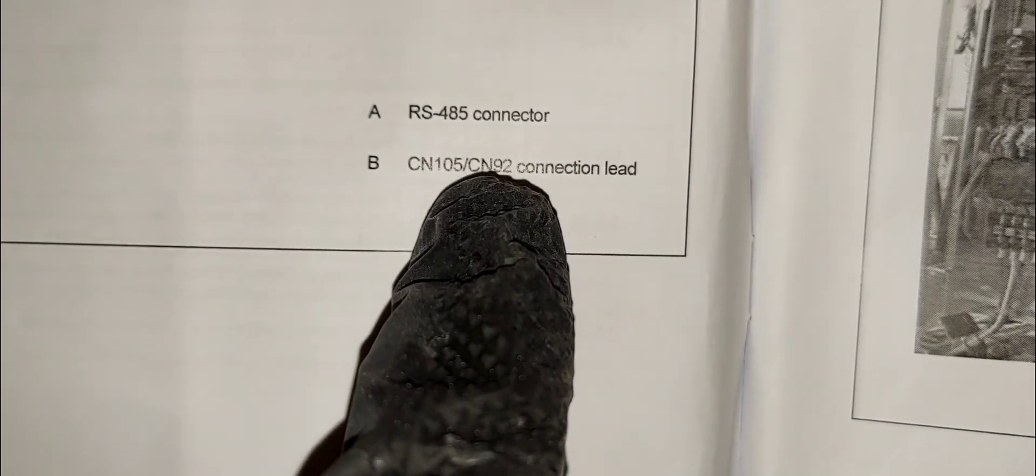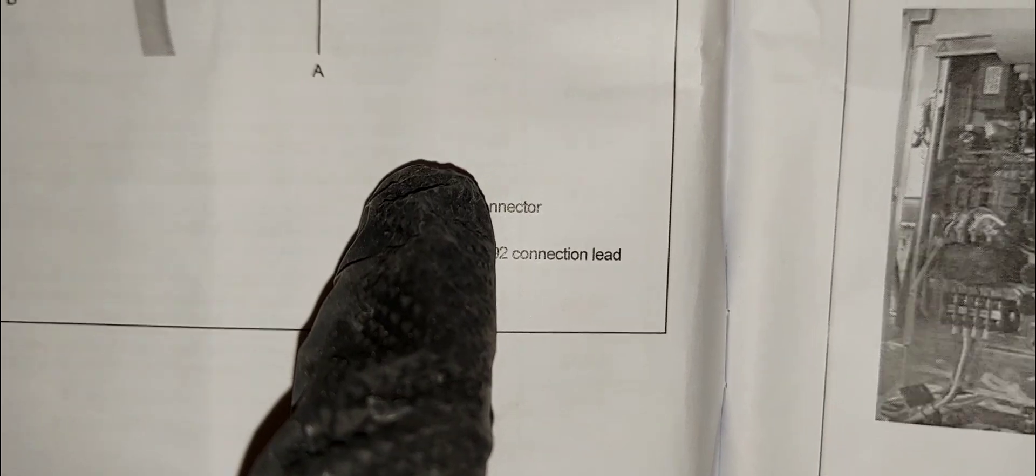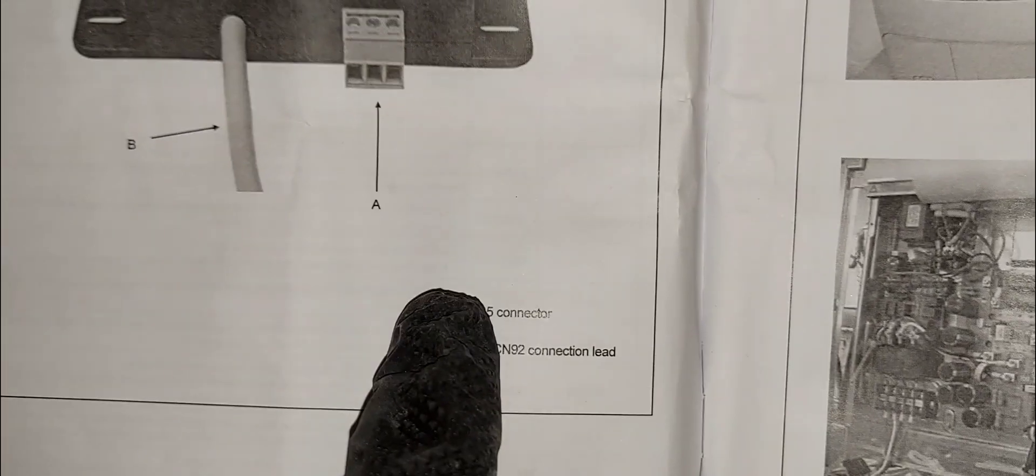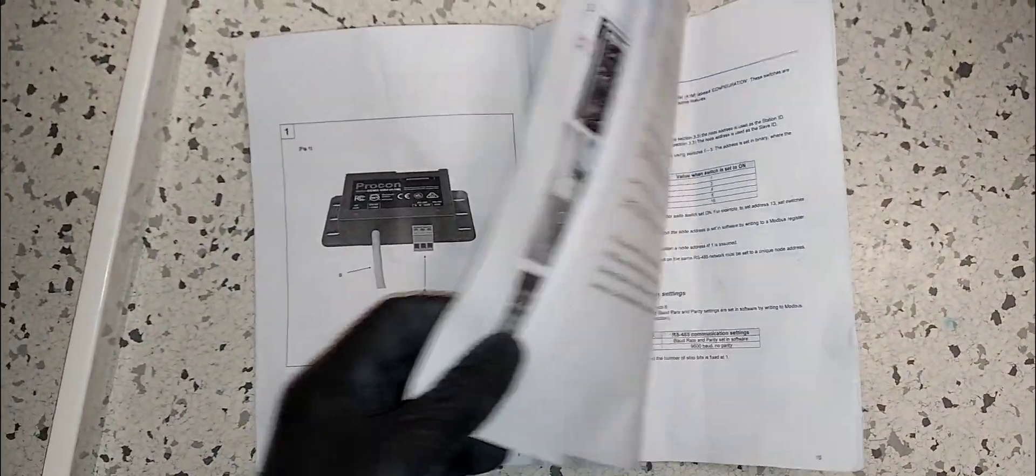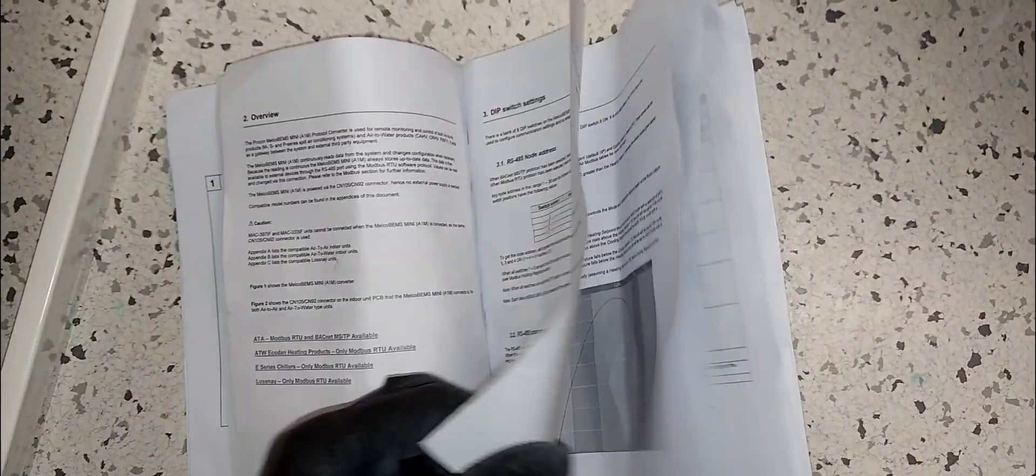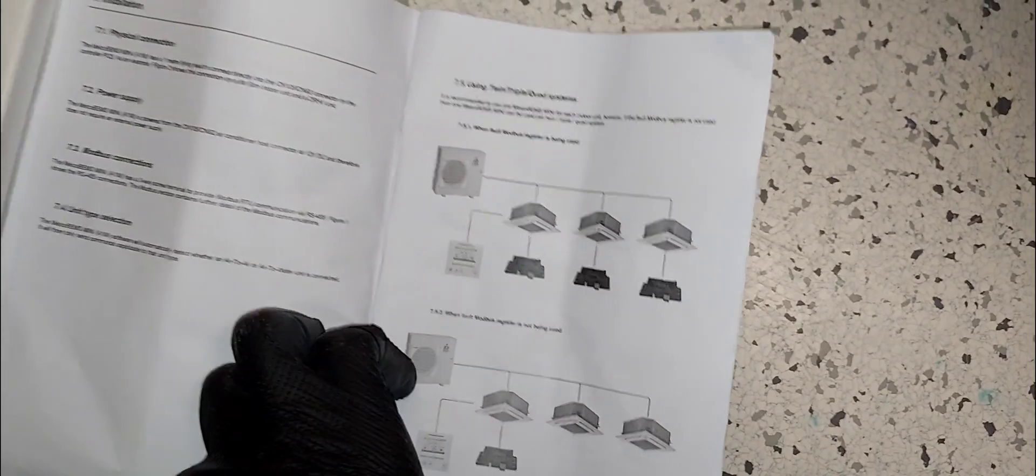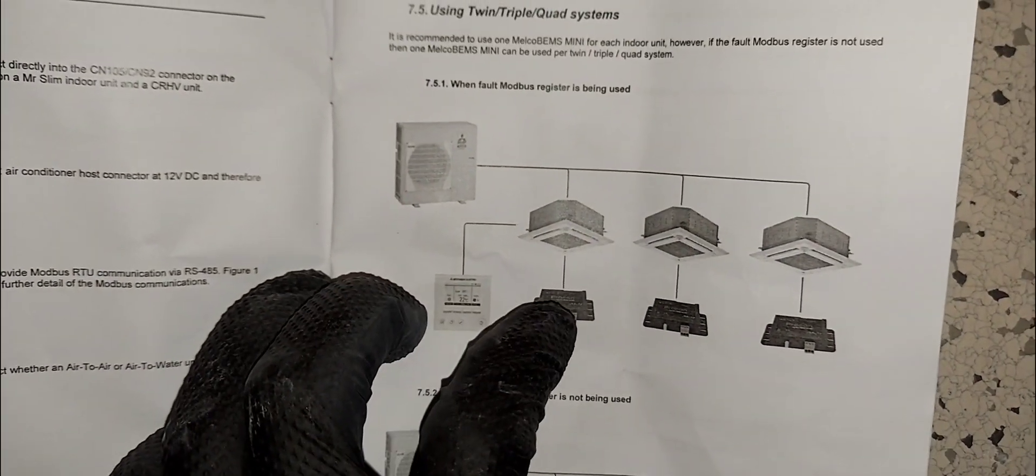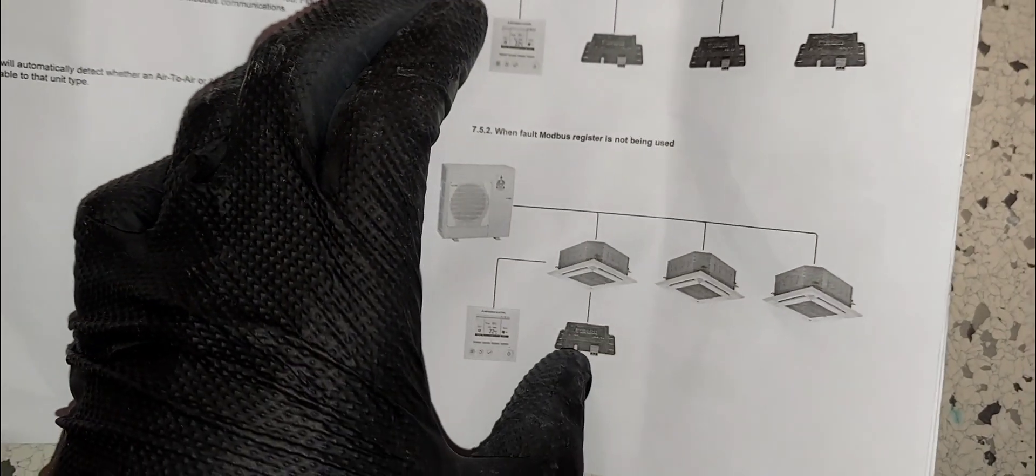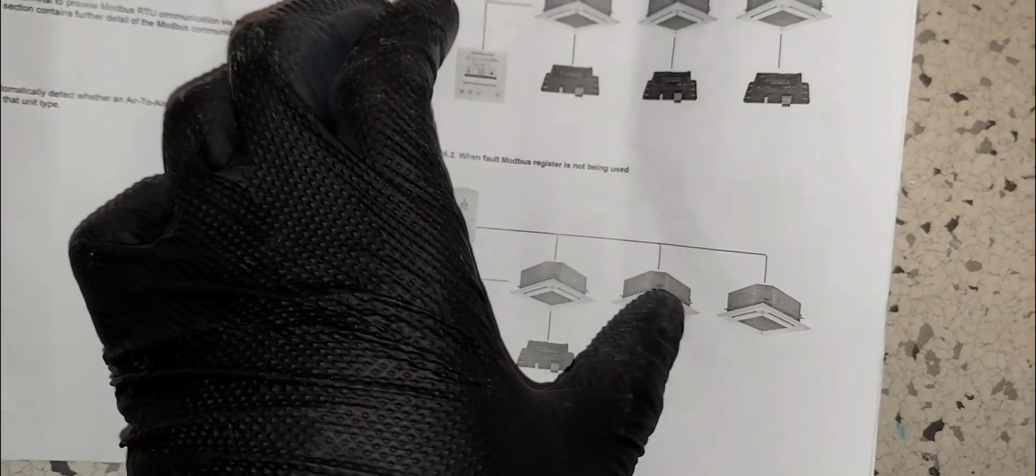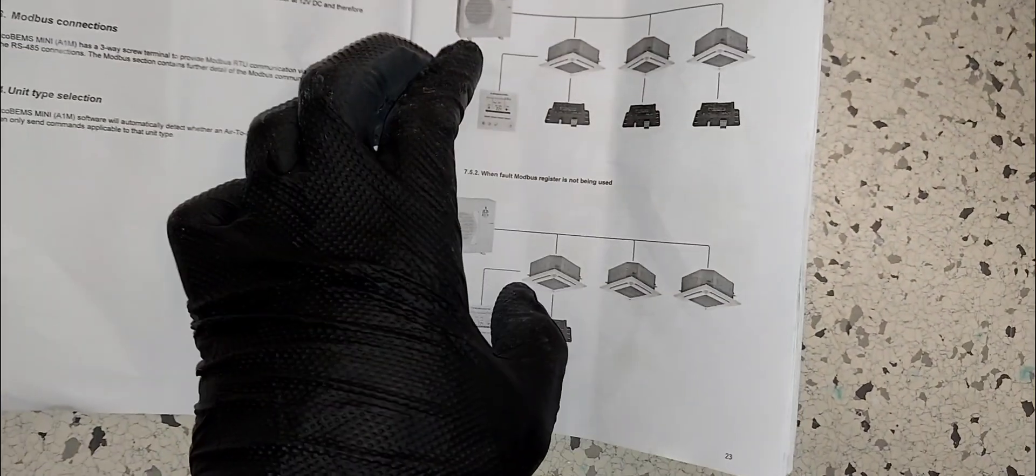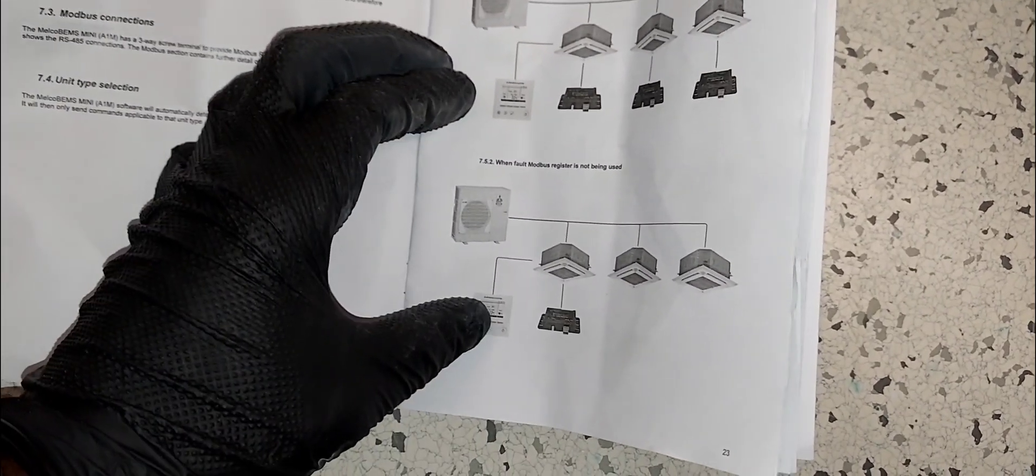CN105 or CN92 - this one right here is your BMS communication. Modbus, it does Modbus. Here's the configurations - you can do one node per indoor unit or you could do one node for three. I think you can do up to four indoor units with one node and you can control them as a group.